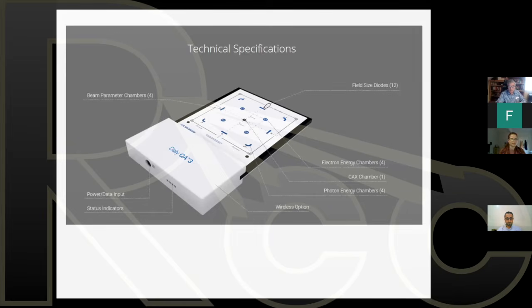Now, if you want to get even more creative with that single device, you would put it in the center here for output, but you could lay a piece of graph paper on the table and you could check it here and here and here and here and check your symmetry and flatness, because it will give you those numbers. So even at the very least, if you don't have the funds for something as technical as this, you can still make up a device with either a diode or a chamber and still check output, flatness, and symmetry. And you would have to set it up on a piece of graph paper and have ranges, and the therapist could do it that way. A little more time consuming, but still gives you the same confidence that the machine is running correctly that day.